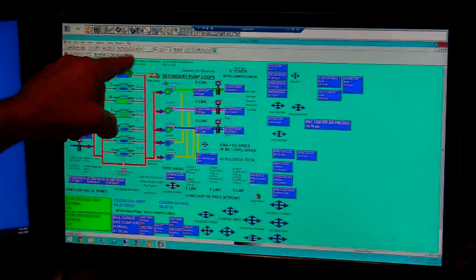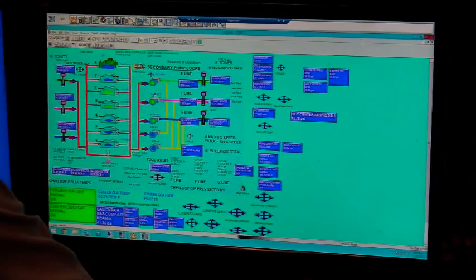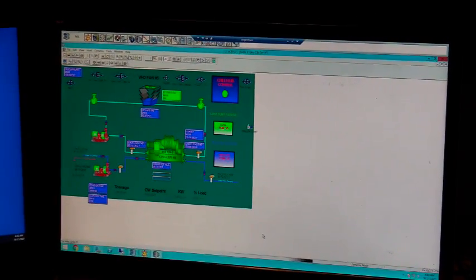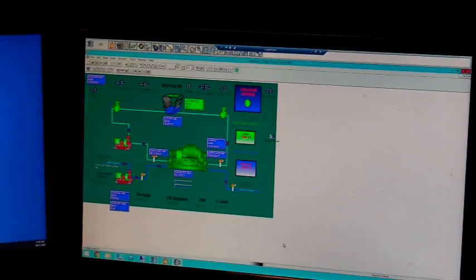What I do is look at the loads on the chillers, right here, just to see what kind of load I'm pulling. I'm pulling 108 because it's calculated with the supply water temperature and the return temperature, and it gets BTUs that way. That gives me what my percentage of the load is.